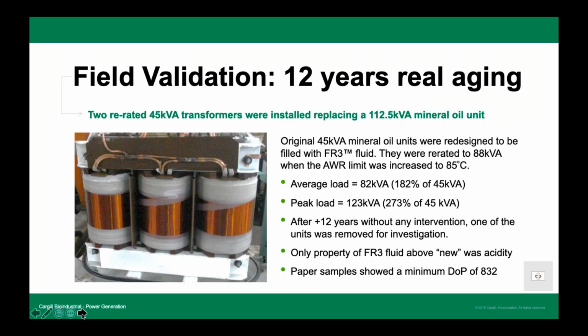Quickly, I will cover one case study. This is from Brazil. A lot of people might have seen it, but I thought to bring it here. They did a study. They had some rating of transformer and wanted to do a standardization. So they put a 45 kVA transformer in place of a 112.5 kVA one. The average annual loading of this transformer was 82 kVA. That means it was running throughout at almost double the rating of the transformer. It was copper wound, filled with natural ester FR3. Let's move to the next slide.